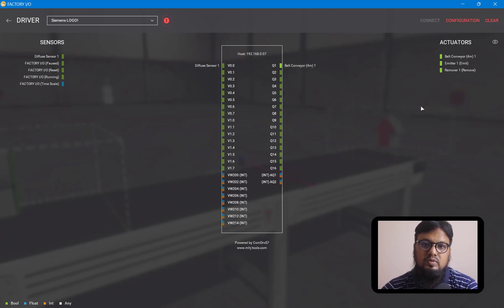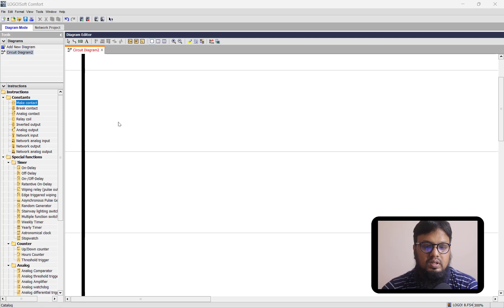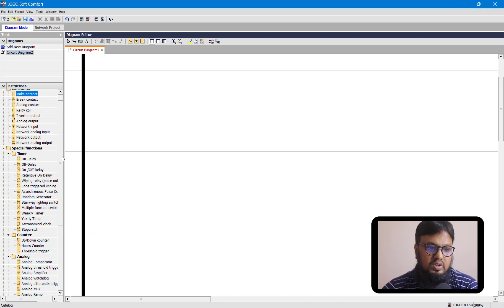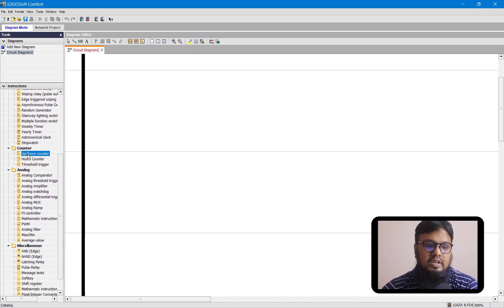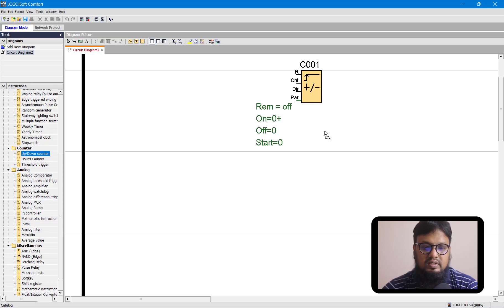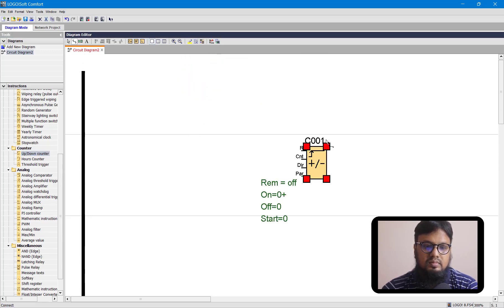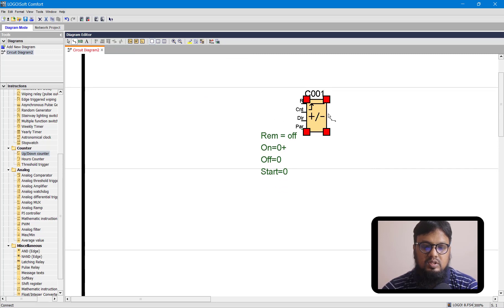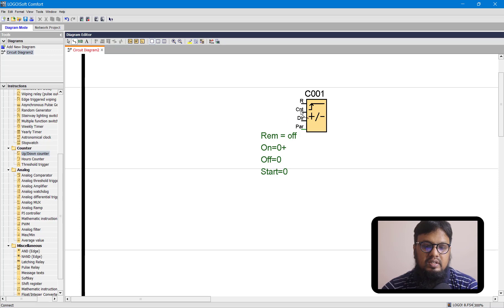Now let's go to LOGO! Soft Comfort software to design our ladder diagram. In the LOGO! Soft Comfort software, we have a special block for counting objects. This block is under the counter tab. Here we have an up-down counter. This up-down counter can take three inputs: the first is R for reset, the second is count, and the third is for direction — meaning it can count upward or downward. For counting, we will connect a sensor to the count pin first.